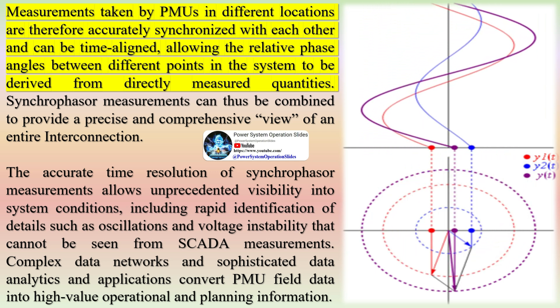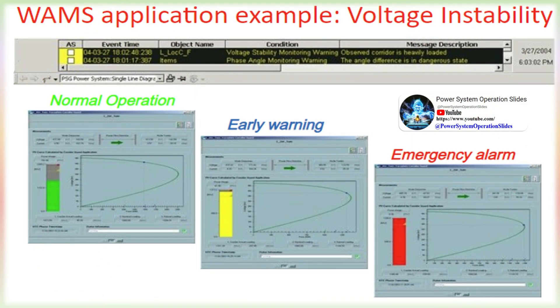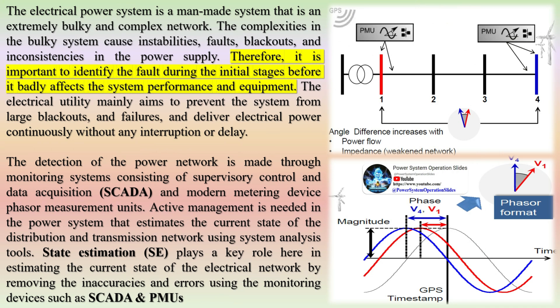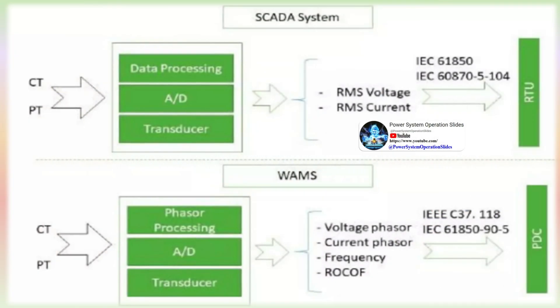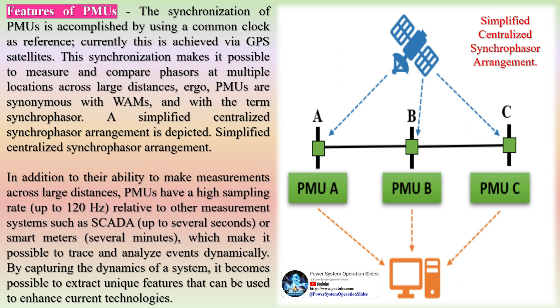A synchrophasor is a time-synchronized measurement of a quantity described by a phasor. Like a vector, a phasor has magnitude and phase information. Devices called phasor measurement units (PMU) measure voltage and current, and with these measurements derive parameters such as frequency and phase angle. The measurements may be either fundamental components at 50 or 60 Hz, and of the positive sequence for the three-phase representation. Data reporting rates are typically 30 to 60 records per second. In contrast, current SCADA systems often report data every 4 to 6 seconds — over a hundred times slower than PMUs.